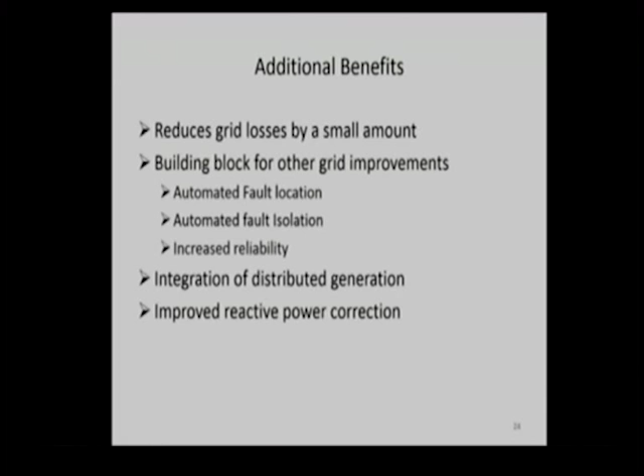The other thing is that CVR is a building block for other grid improvements. You're putting a communication system out in the grid, you're putting metering out in the grid, and these are really building blocks for automated fault location, fault isolation, and increased reliability. There's also an advantage in integrating distributed generation. When the utility has metering out in the grid, they can see problems that start occurring when you have a lot of distributed generation. Maybe it's a bright day and the load is actually low because it's not hot, so you've got a lot of solar producing. You need to lower the grid voltage a little bit, and this system will allow that to happen in an automated way. And it also improves reactive power.